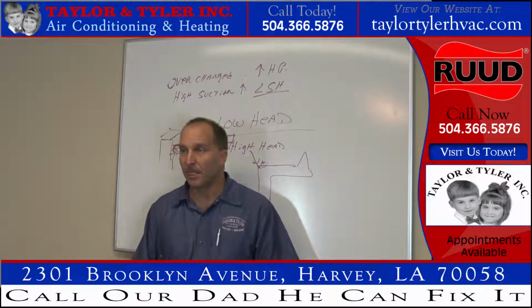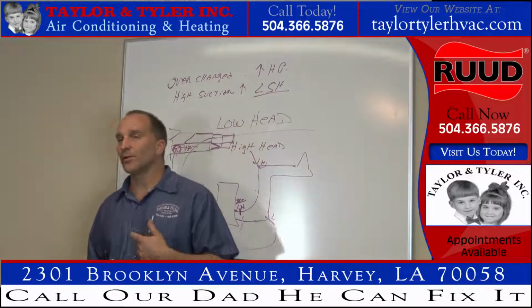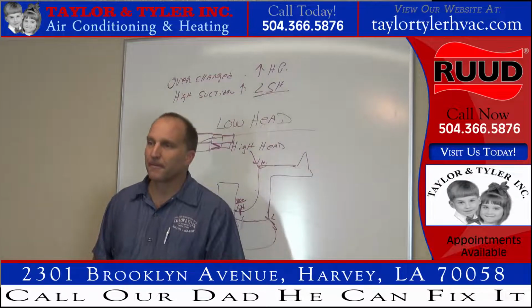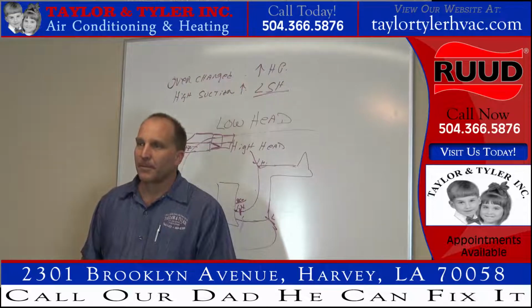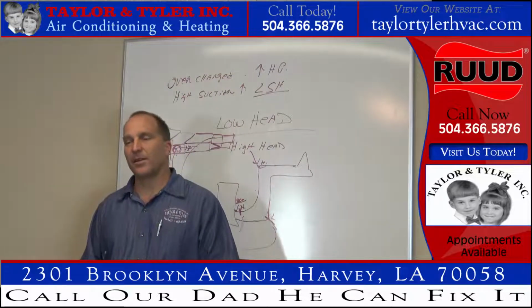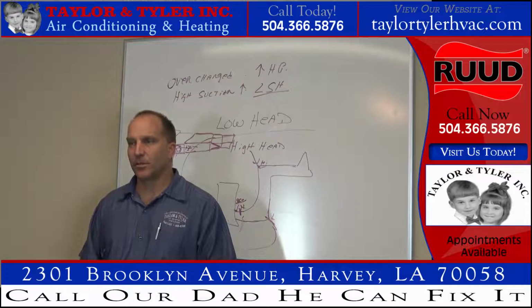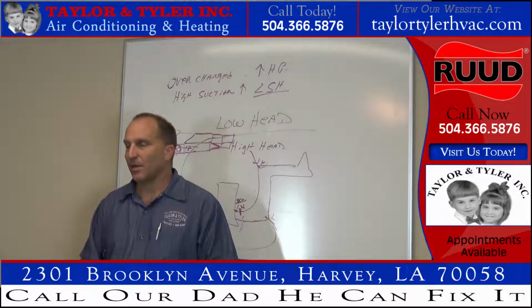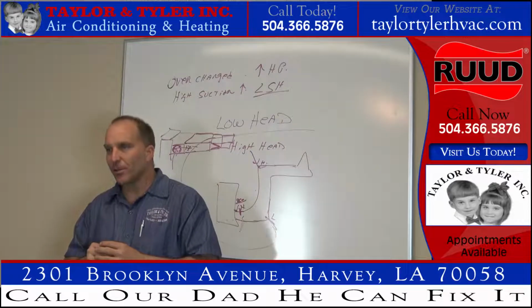Okay? If a system's low on refrigerant, do you have a high superheat? Yes. What if you have a TXV that's slightly undercharged? You're not going to see it, because it maintains a constant superheat.